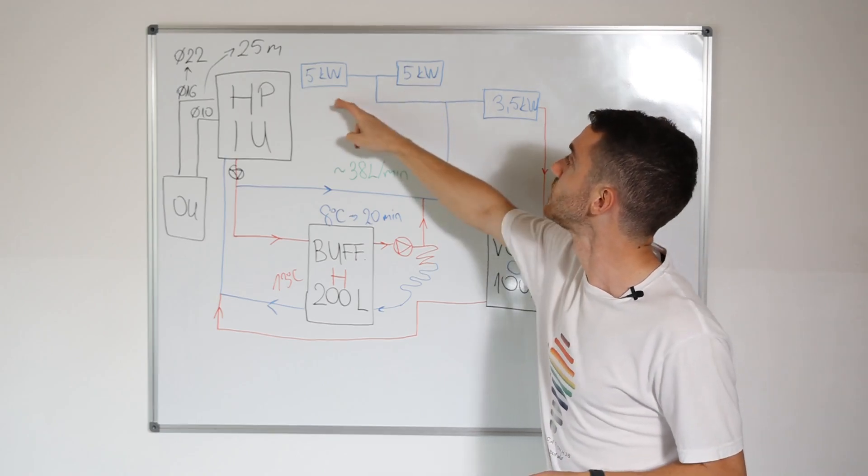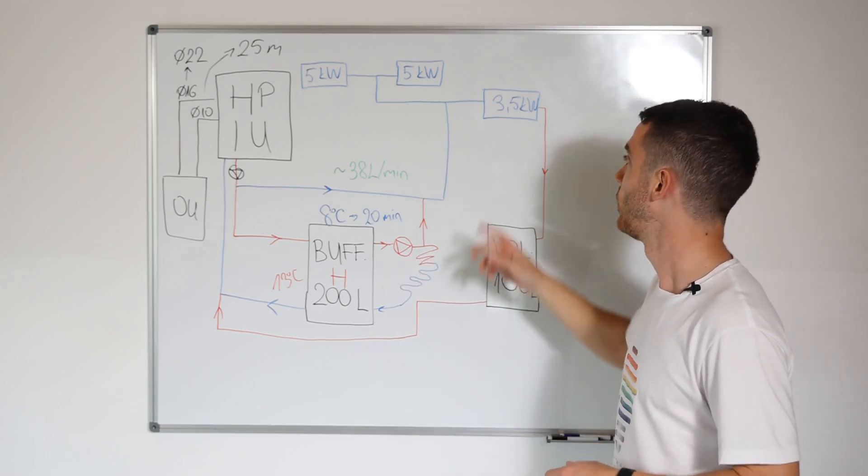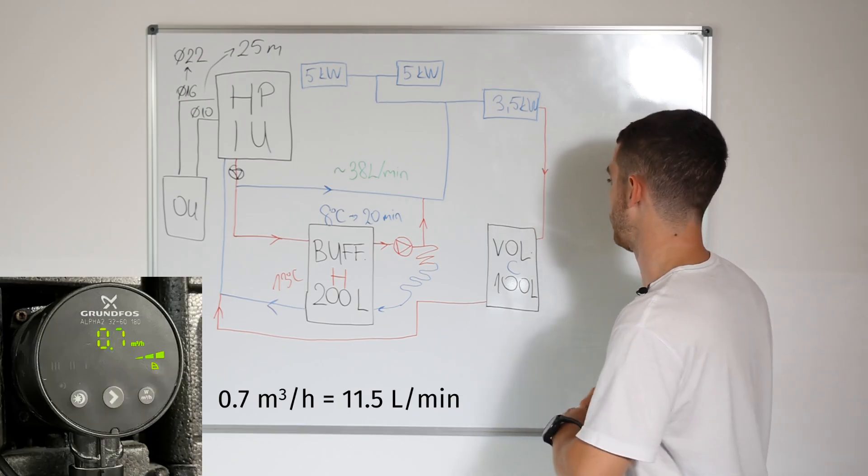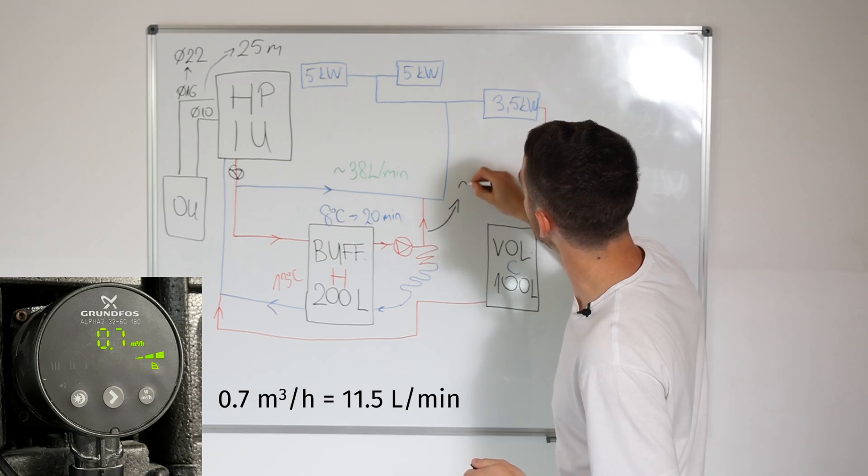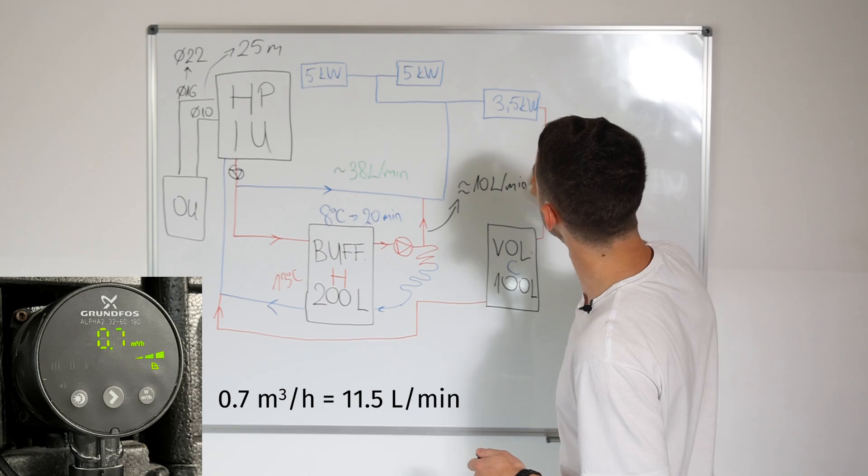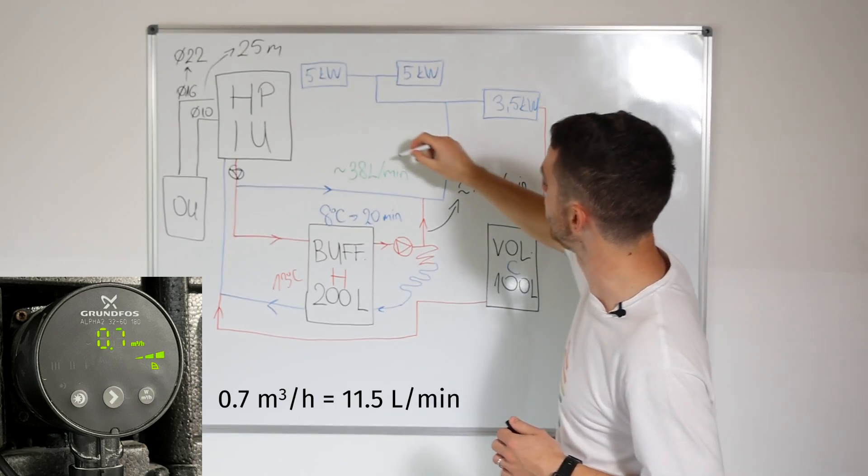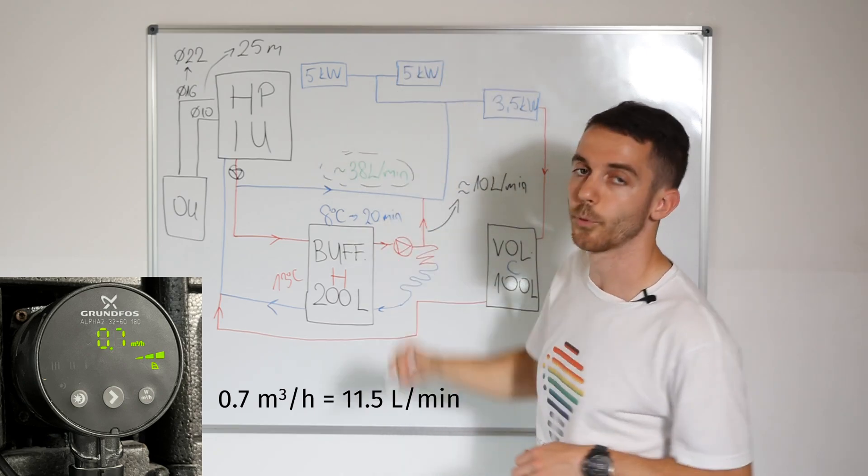When we put, when we turn on these two, it's not working. And on Grundfos pump, when all three were on, we can see that flow rate here is around 10 liters per minute. So this is enough for one fan coil for 3.5. What we need, we need 38 liters per minute for 13.5 kilowatt.